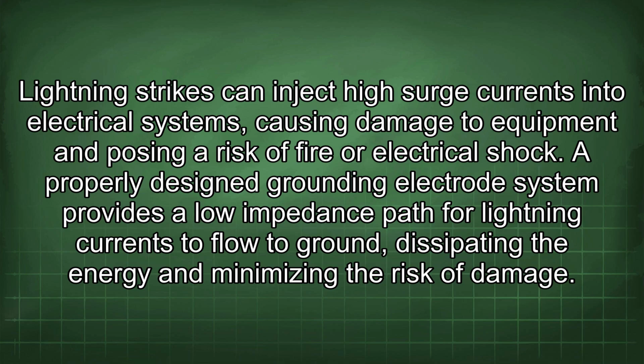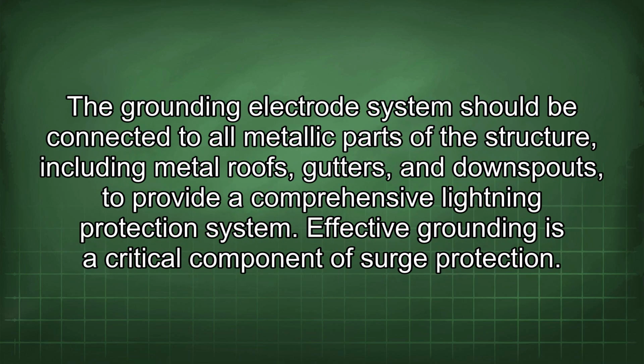Lightning strikes can inject high surge currents into electrical systems, causing damage to equipment and posing a risk of fire or electrical shock. A properly designed grounding electrode system provides a low impedance path for lightning currents to flow to ground, dissipating the energy and minimizing the risk of damage. The grounding electrode system should be connected to all metallic parts of the structure, including metal roofs, gutters, and downspouts, to provide a comprehensive lightning protection system.